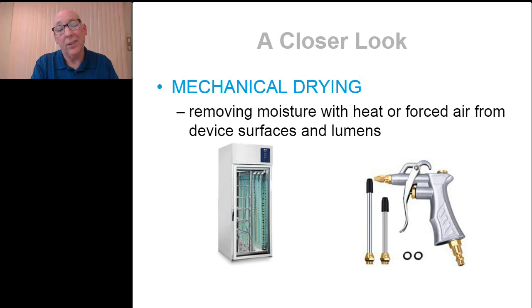Now, you may have independent air pumps that are optional, that may be in drying cabinets, that can dry tubing, long lumens, et cetera, such as endoscope channels. So mechanical drying certainly speeds up the process. It can be very effective because it's not only circulating air through internal components, but it's also warming the air. And it goes right back to that term we spoke about earlier, evaporation. And that will speed up the evaporation of moisture to dry the surface itself, especially those internal surfaces.